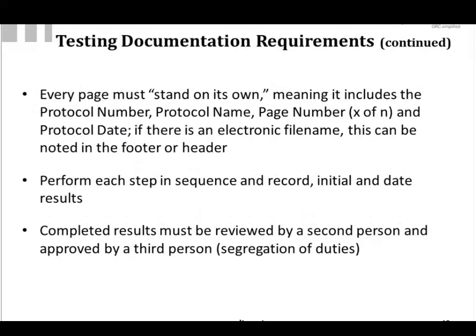And every page in your protocol has to stand on its own. So that means that it has to include on each page, and usually in the header, the protocol number, protocol name, the page number as X page of N pages, and the protocol date. And if there is an electronic file name, that should be noted in the footer or header as well.